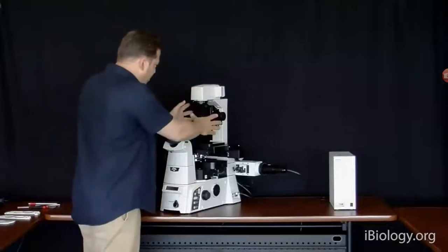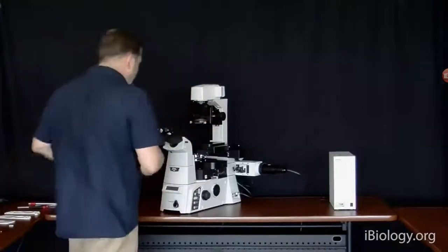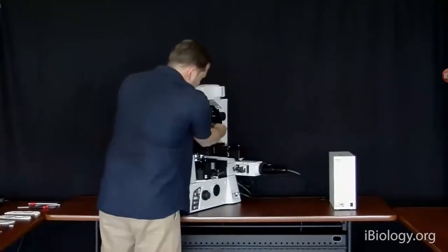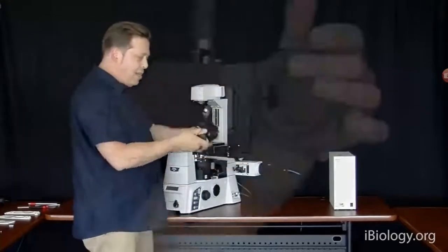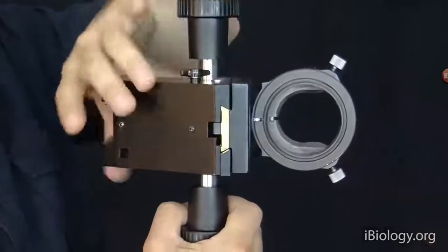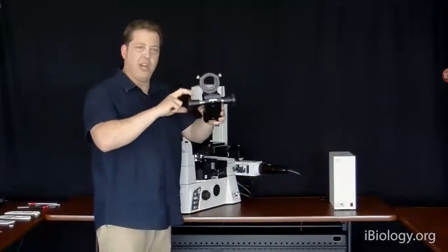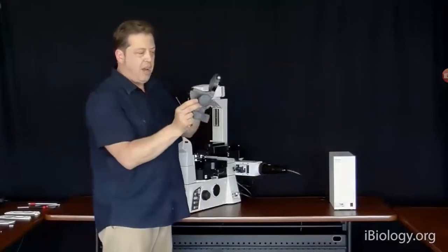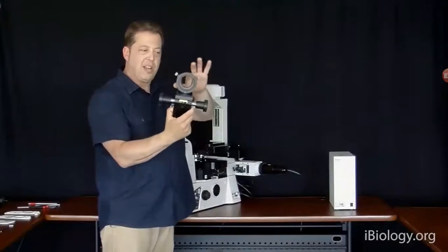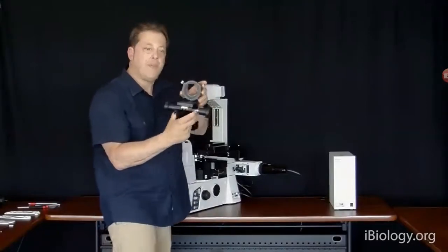So now we've removed many of the components on the transmitted light arm. One of the last components here is the condenser mount and condenser focus unit. And that just loosens and slides off on the dovetail here. And it's basically a solid brass adjustable mount, and it has a focus on it. And as I had mentioned, this will allow you to mount additional components for doing techniques. So it just gives you a focusability, and it's centered on the optical axis of the microscope.